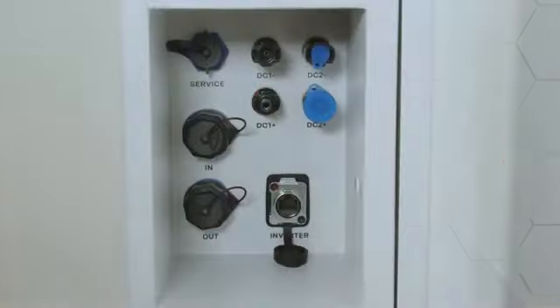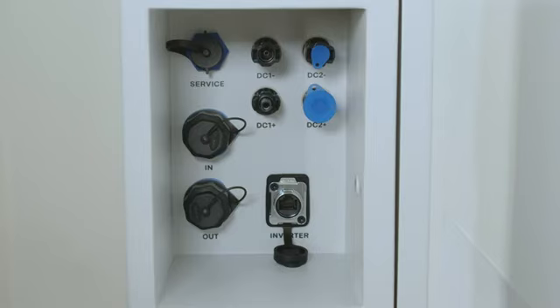Regarding the DC connection of the battery, please note that we start with the Amphenol DC connectors. However, from fall 2025 we will start with MC4 Stäubli Evo Stor connectors, so that you have a standard DC connection port with MC4. Whenever you want to install one single hybrid inverter to one single battery tower, you can do this by using the DC1 plus and DC1 minus. Whenever you want to install multiple battery towers for a parallel connection, you can do this by using the DC 2 plus and DC 2 minus plug, and therefore directly connect multiple battery towers in parallel without the need of a DC combiner box.